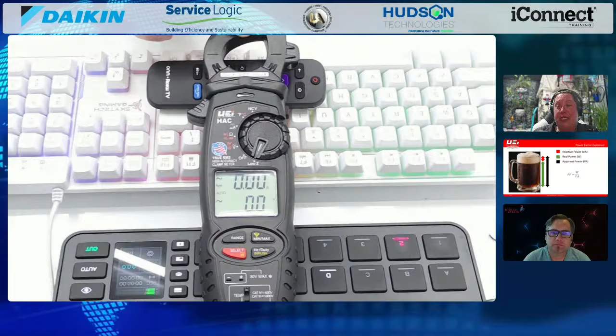But the DL599, we've had that one for a while now, and it's been a very solid meter. The HAC, though, has some different functionalities on it, so it doesn't have the three-phase motor rotation testing. But what it really does incredibly well is the low amp reading, because when we think about the equipment we have now, it's such a smaller amp draw that we're pulling off that equipment, it's hard for it to be accurate. So we really set a new gold standard in accuracy when looking at low amps. This is going to make it much easier to make sure the equipment is actually working properly, because it's so accurate through that clamp.